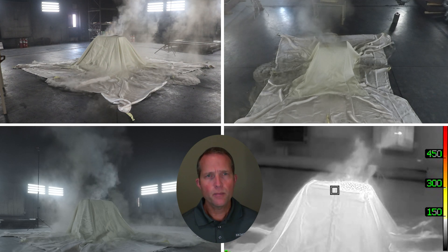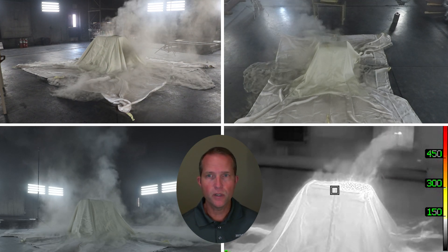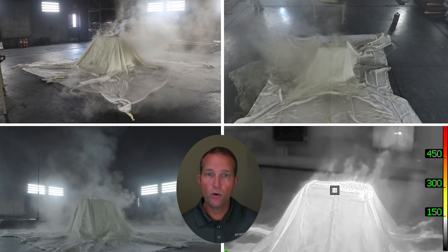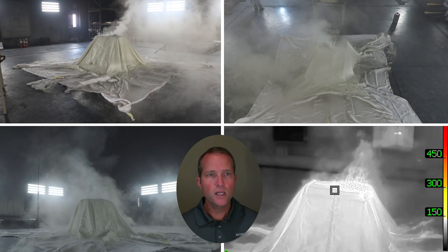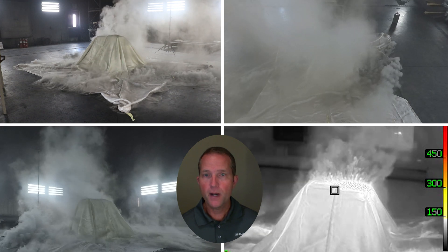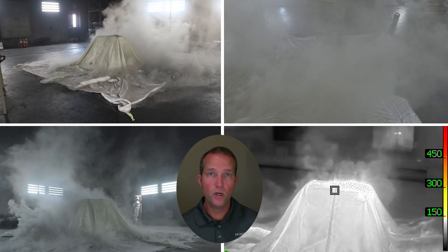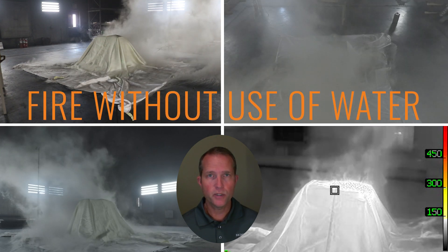That said, because the progression of the fire has been slowed somewhat, any venting that exists in the building can be more effective, and since our heavy-duty blankets are permeable, they have a tendency to filter some of that smoke and greatly reduce its overall velocity. The room will likely therefore fill at a slower rate. Keep in mind that the smoke is still hazardous, so venting the room is recommended to avoid a potential explosion. It is also imperative that anyone in the room wear appropriate respiratory protection.